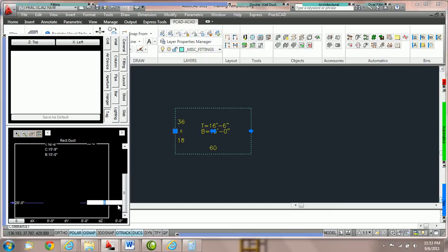In other words, even if this is set so it's not relative bottom, here you can see it's targeting this mark. This tag takes the absolute elevation and subtracts the relative 0 mark. So the first step on every drawing is to open up your drawing, find out what your new 0 is, or your new reference point, put it in as 0.0, and then set it to relative bottom to start.